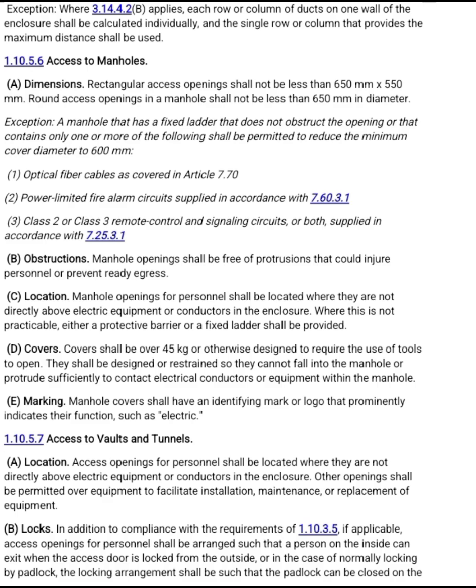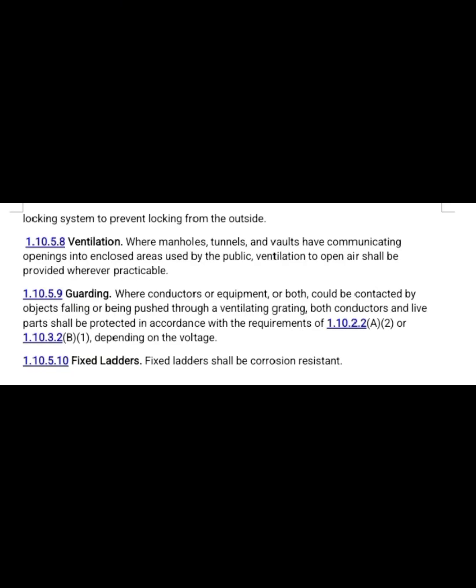1.10.5.7 Access to vaults and tunnels. A. Location. Access openings for personnel shall be located where they are not directly above electrical equipment or conductors in the enclosure. Other openings shall be permitted over equipment to facilitate installation, maintenance, or replacement of equipment. B. Locks. In addition to compliance with the requirements of 1.10.3.5, if applicable, access openings for personnel shall be arranged such that a person on the inside can exit when the access door is locked from the outside, or in the case of normally locking by padlock, the locking arrangements shall be such that the padlock can be closed on the locking system to prevent locking from the outside.